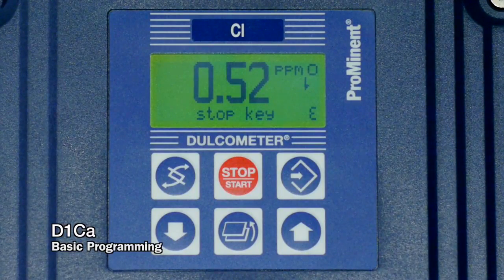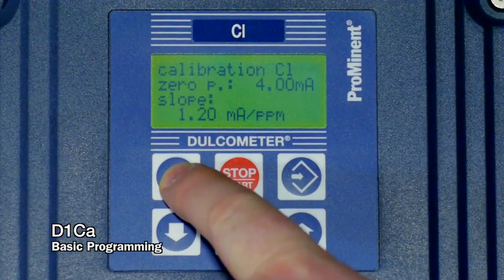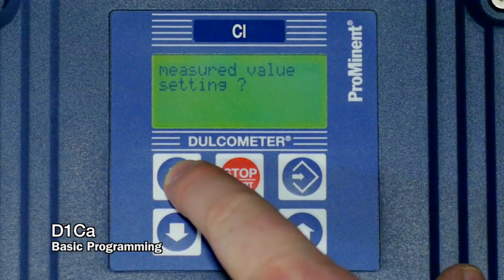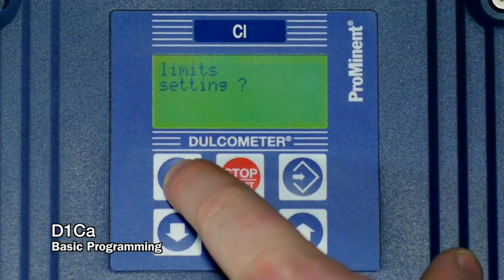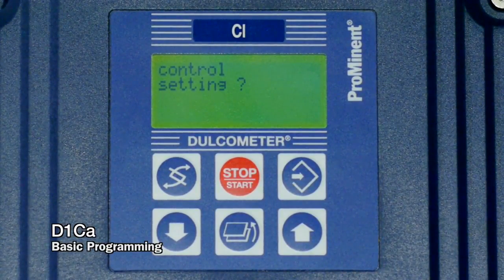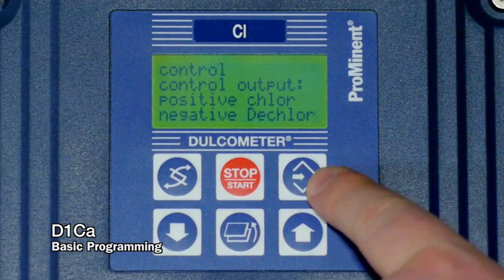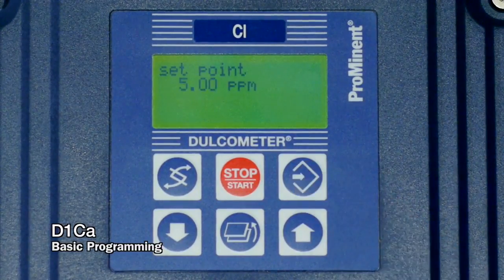Keep in mind that once you change that, one of the things that changes is the set point value. It defaults to half the range of the sensor. So since we told this unit that it's at 10 ppm here on this chlorine unit, it goes to 5 ppm as our set point. That's, in most applications, a very high amount of chlorine. So be careful and be aware of that. The next thing we want to do is change our set point. We can do that in either the complete or reduced menu. So we can continue to press the change key until you see the control settings screen. If we want to get into that menu, we press the enter button. So we'll continue to press the enter button until we see set point.